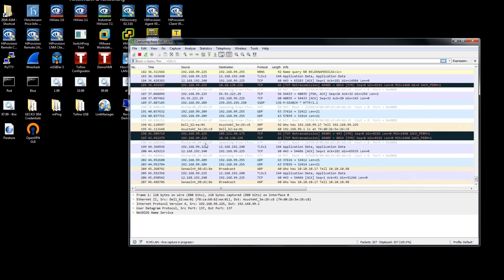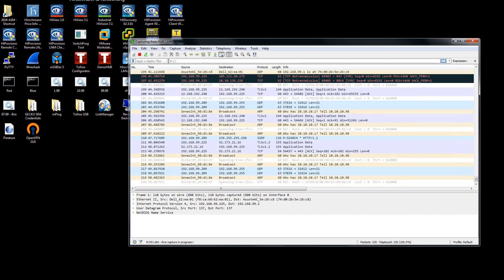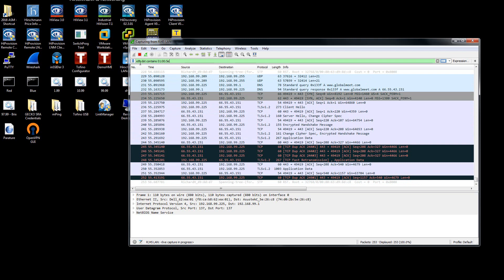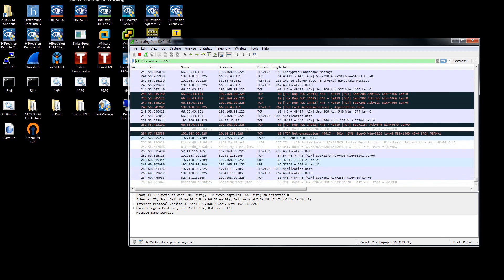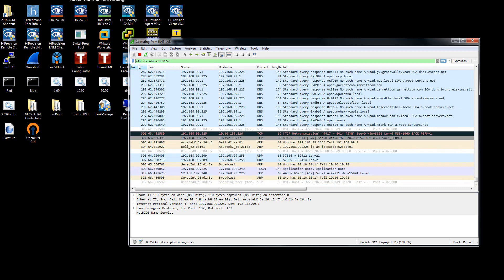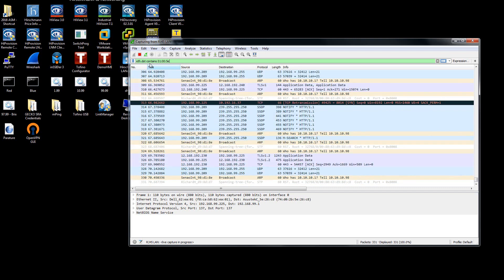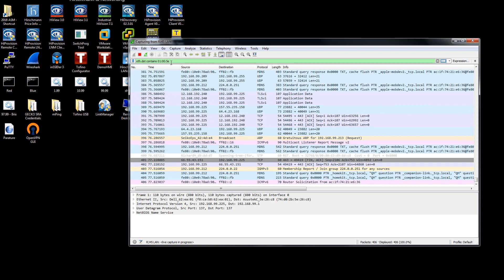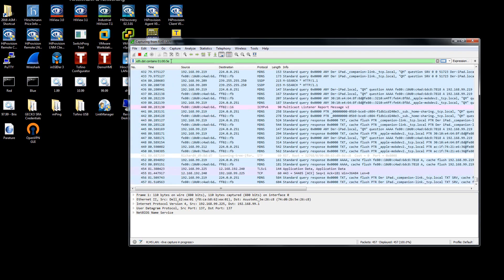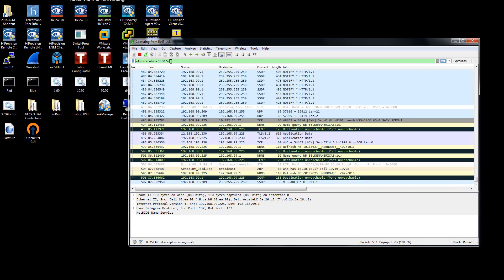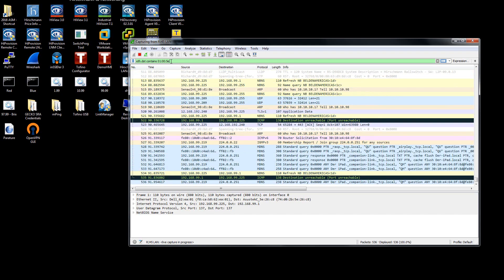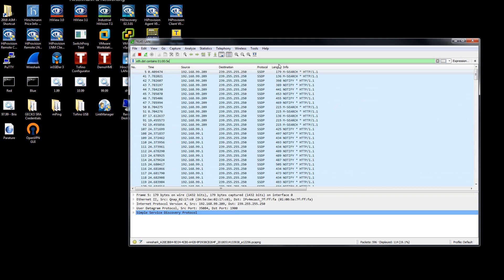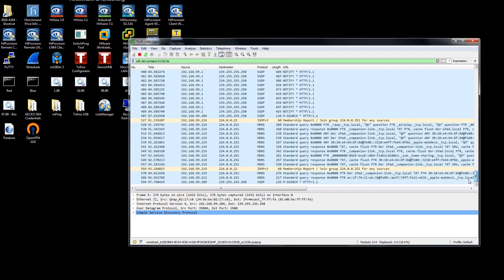But instead of seeing everything, I specifically just want to see multicast traffic. So what I can do is apply a display filter here. The display filter that I'm going to put in is eth.dst contains 01005e. So a multicast packet that would hit a switch is going to have the destination MAC address that starts with 01005e. I'll then hit enter.